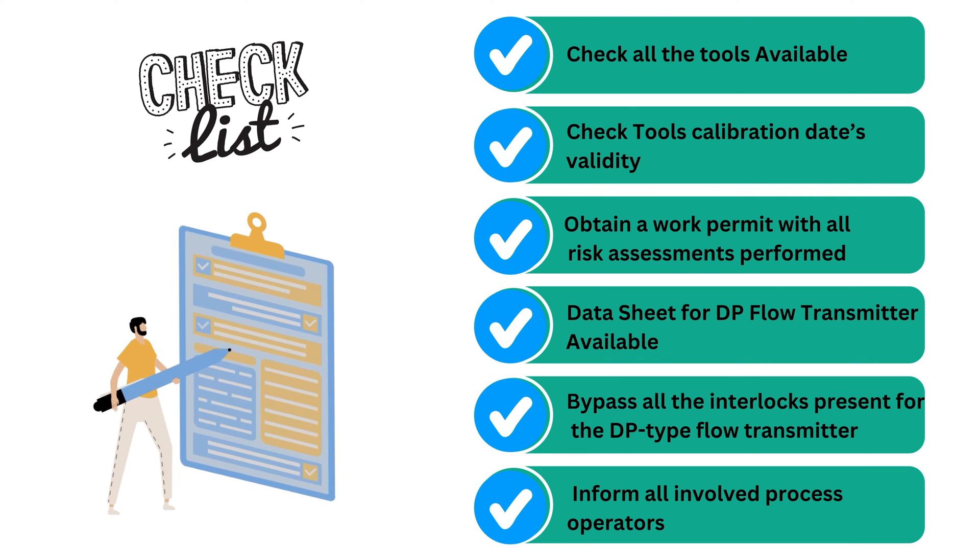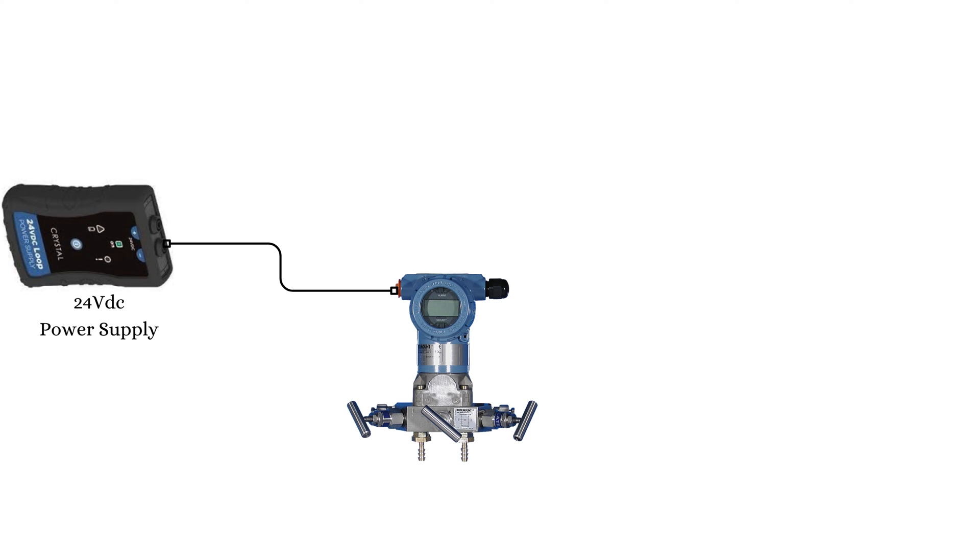The DP type flow transmitter calibration procedure: when all the preparatory work has been completed, we can now start calibrating the DP flow transmitter. Arrange all the tools. The DP type flow transmitter can be powered through the field cables connecting the DP transmitter to the system or by using an external power supply.